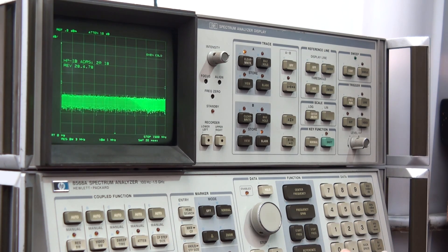It's got a couple of non-volatile memory positions, and they're not for the calibration, but for saving setups. Like you would in quite a lot of bits of equipment. Like on the later sort of HP scopes where you can save and recall settings and it stores your trig points and things. You can do that with this instrument, but it relies on this backup battery.